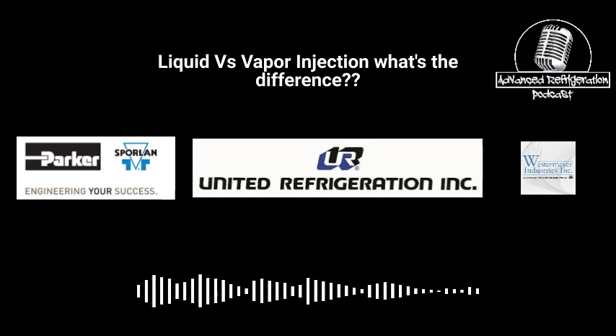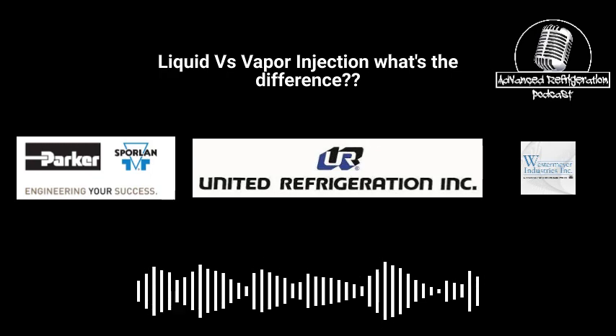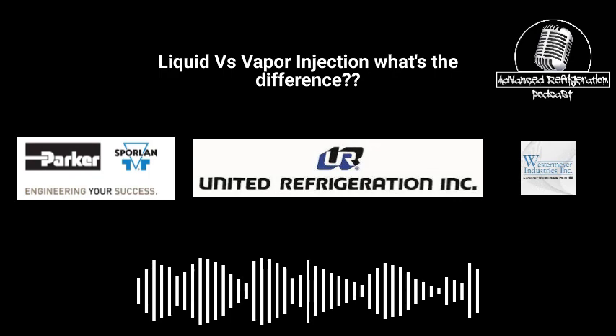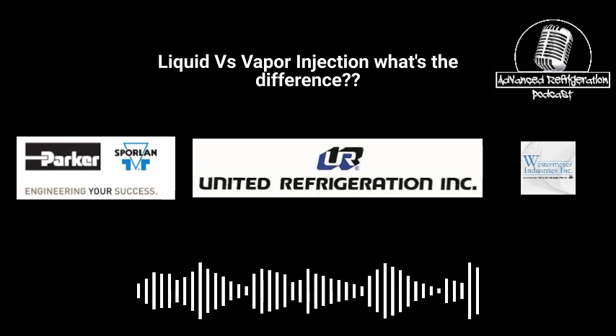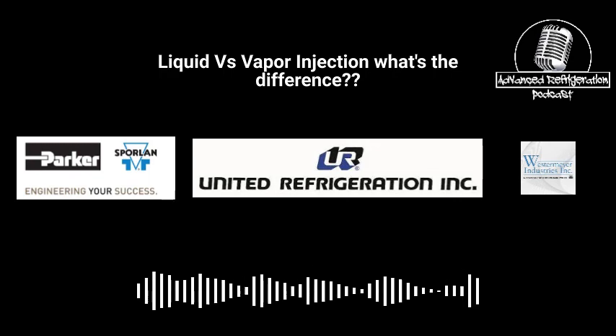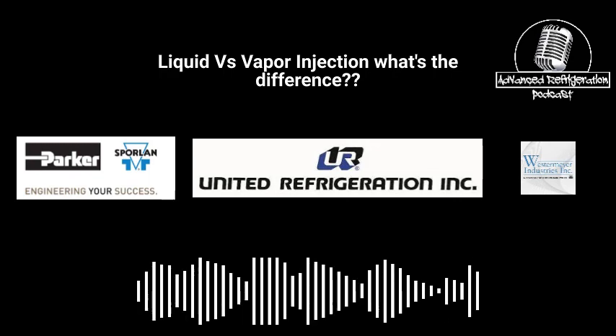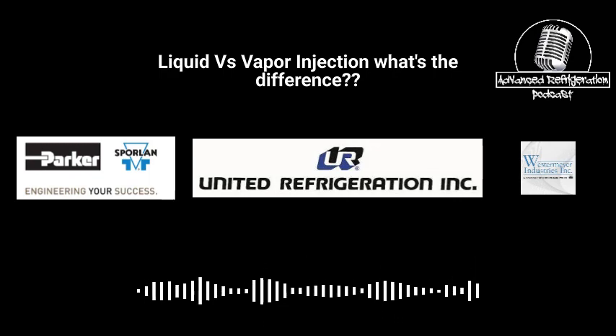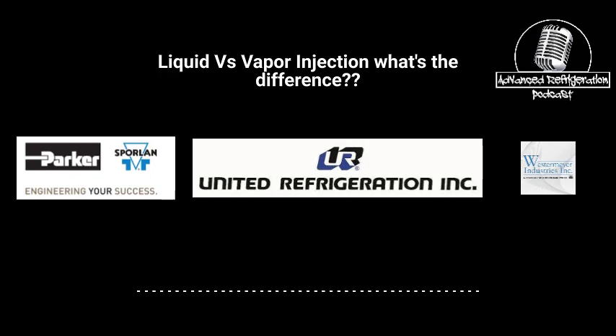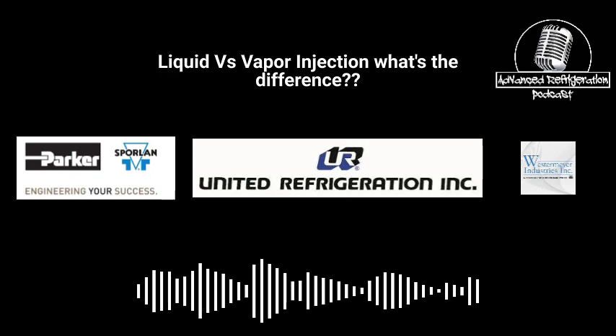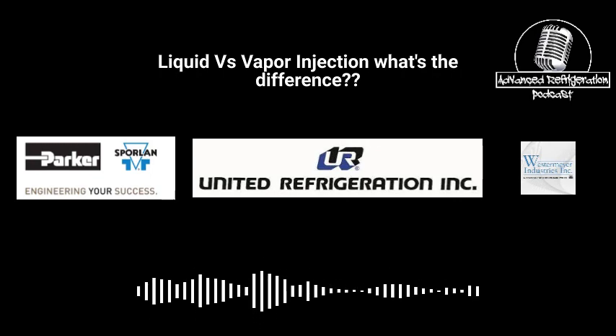Another thing: I've probably been on the phone with, and this isn't a lie, at least 25 different people who say, I've got this compound compressor, this Carlyle, and it keeps grenading all the high stages. Well, typically what happens is, for all the ones that have electronic expansion valves, usually in the program they'll have a fail-safe. So if the temperature of the subcooler goes down too low, it'll shut down the liquid solenoid.